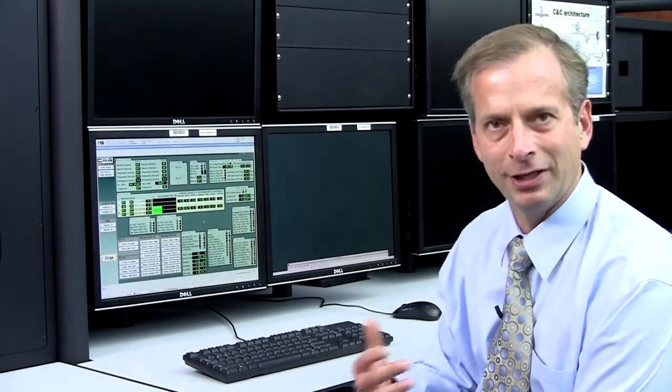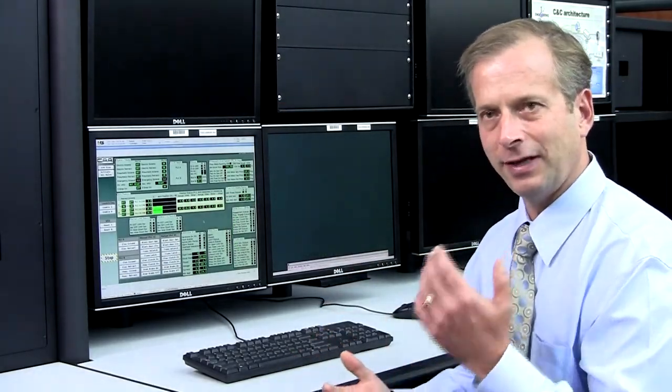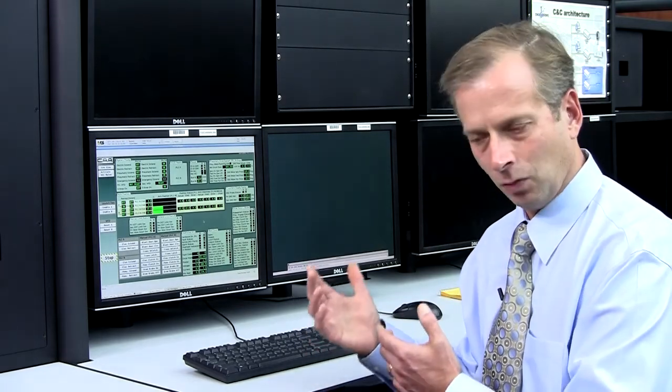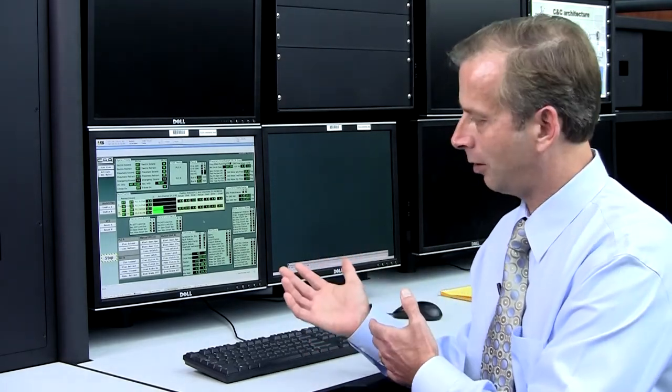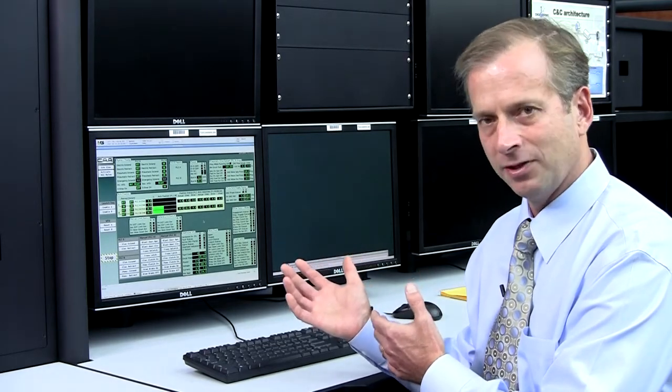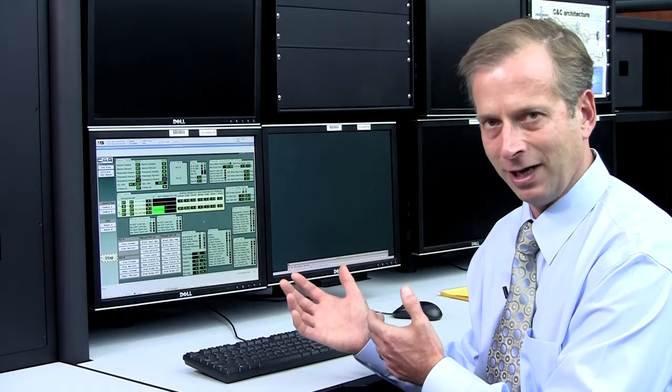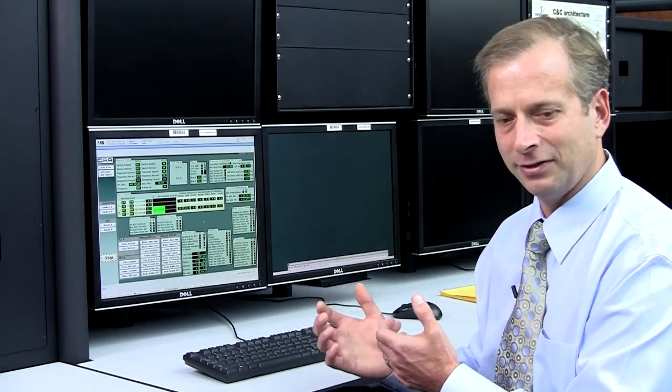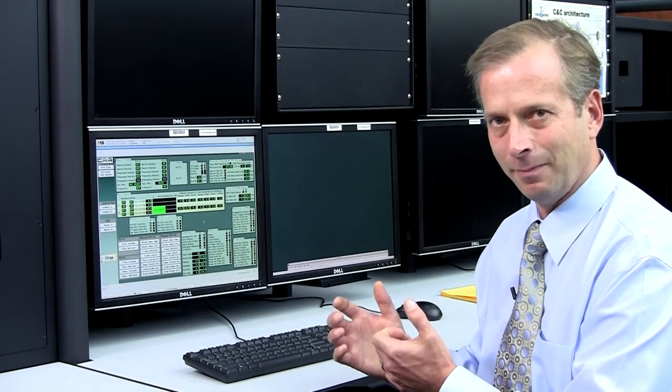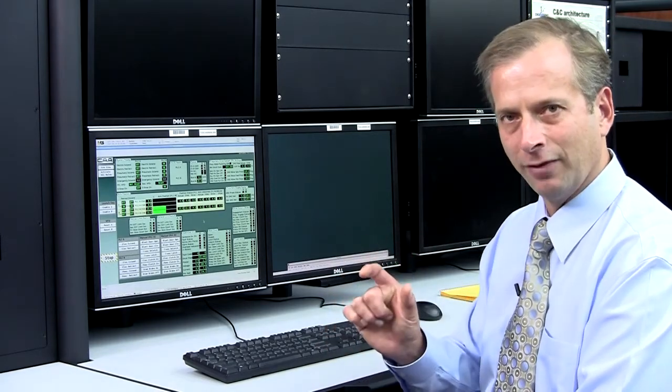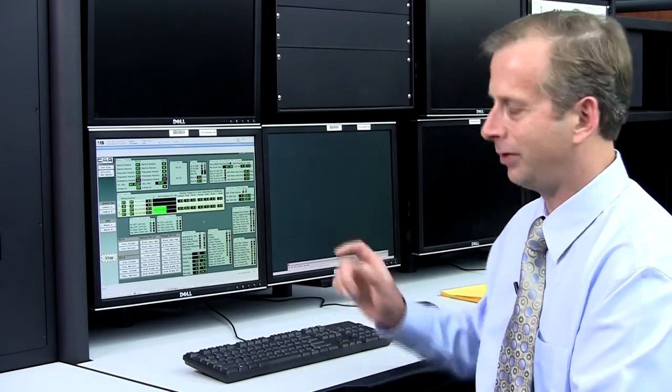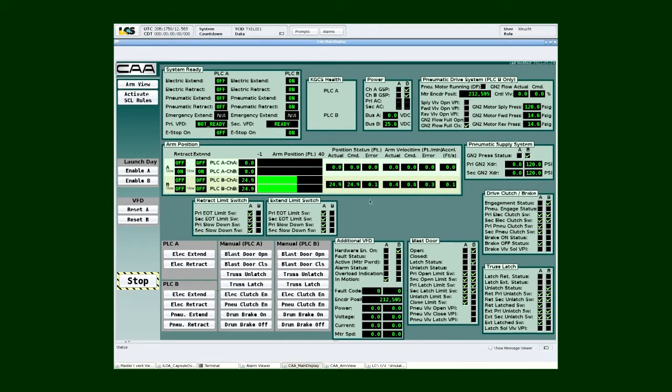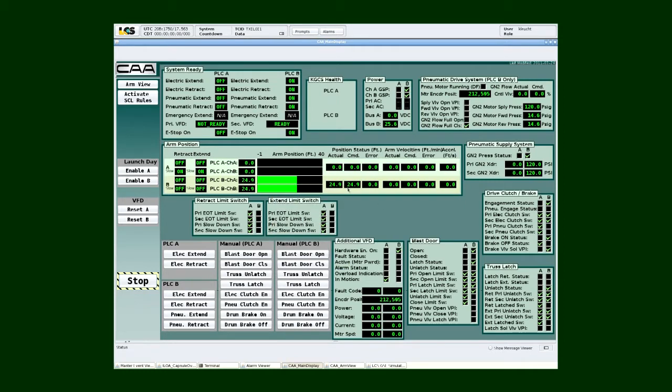What I'm going to do now is I'm going to go ahead and initiate a stop. And because this system has PLC A and PLC B, one of the things that we are going to demonstrate here is we have spacecraft control language applications in our application software framework. And when I initiate a stop, I actually have to send a command to both PLCs because they are independent, but yet we're providing one common point of control for two independent control systems. So when I select stop and I hit send, notice that my arm stops at 24.9 feet. And if you'll notice, my actual velocity information now goes to zero. So my arm did move and decelerate to zero feet per second.